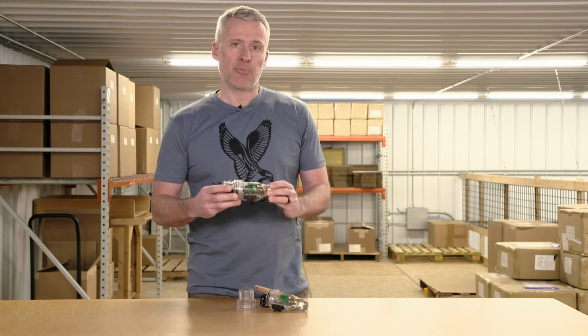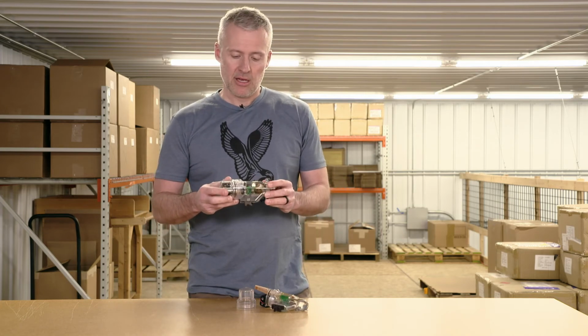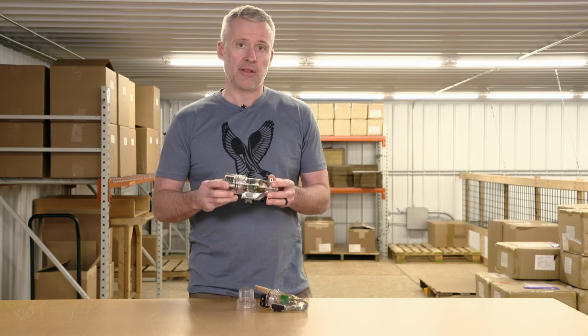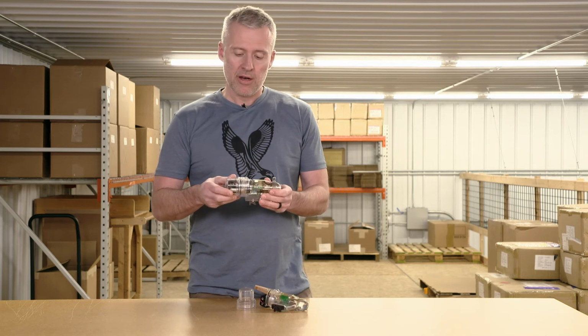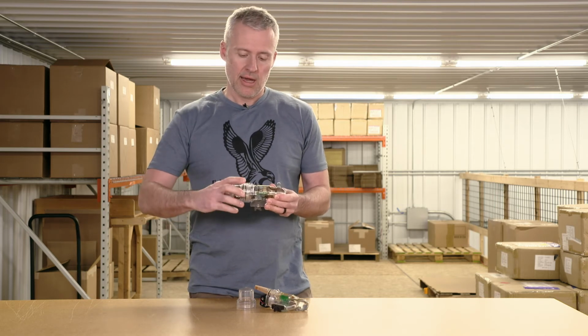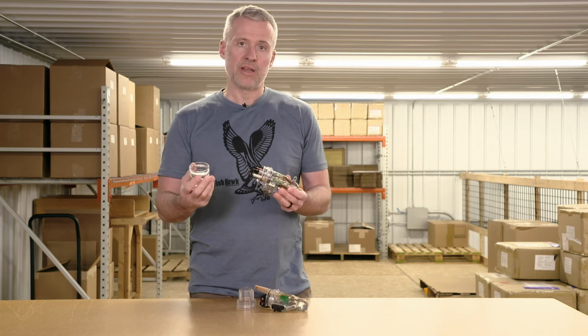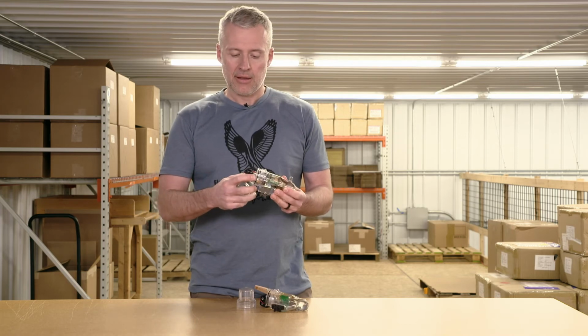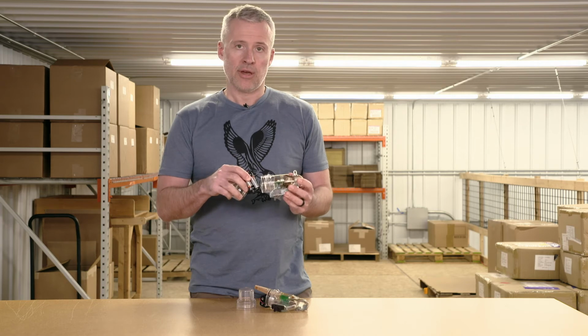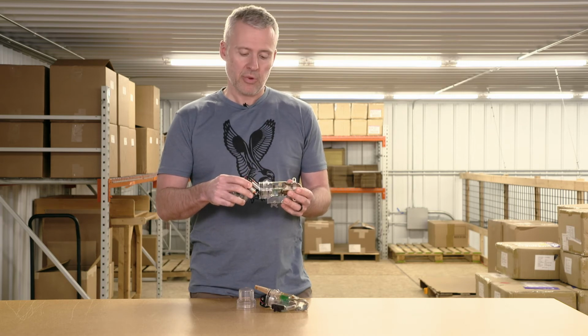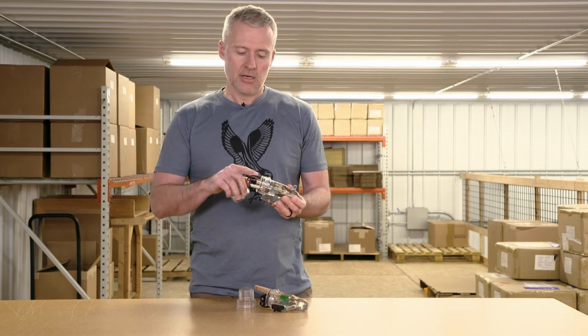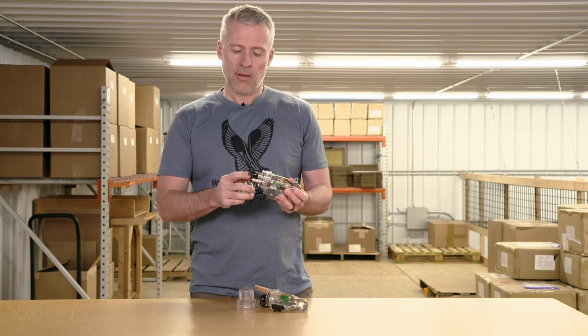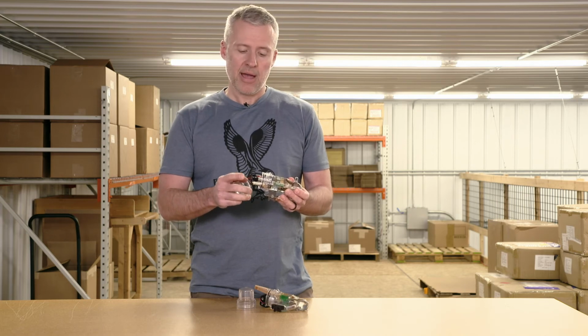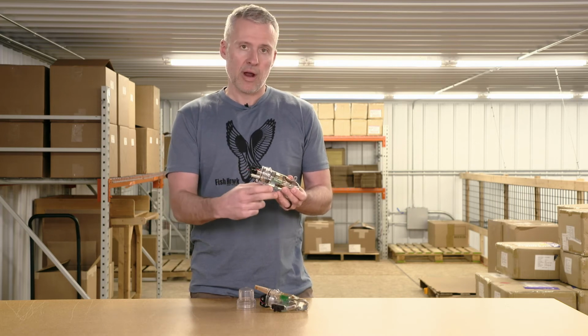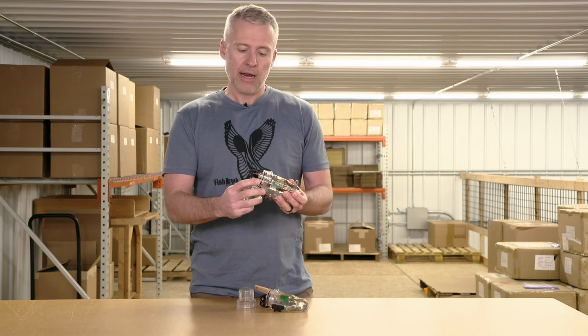Here's a couple other preventative maintenance things that you can do to really extend the life of the battery packs. Number one is to make sure at the end of the day that you're removing the cap to let any of the natural condensation out that creates that corrosion in the first place. The second thing is to make sure that the wires are exiting the back of the battery pack so the wires aren't all crammed up into the front of the probe body.